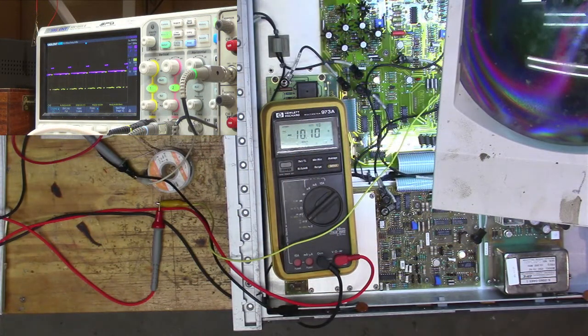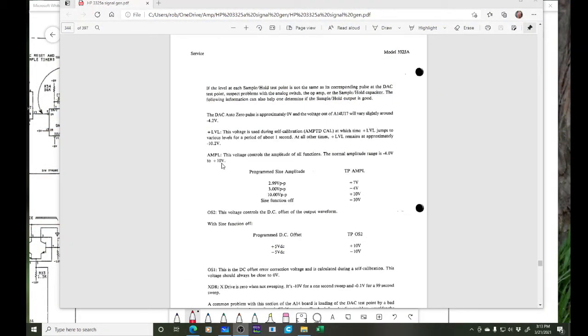Okay, so here's the thing I'm trying to figure out. On this machine, the computer spits out digital values for level, offset, X drive, amplitude, and DC offset. And right now, if you look at the voltmeter there, I'm looking at the value of amplitude. And if I go to the service manual, it says amplitude should be ranged from -4 to +10. It's showing -10, right? And it should be showing one of these values here.